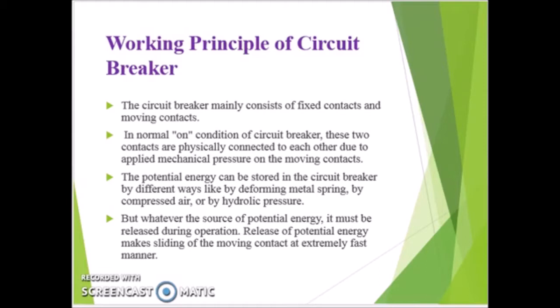In the previous diagram you see the metal spring, but whatever the source of potential energy, it must be released during operation. Release of potential energy makes the moving contact slide in an extremely fast manner. So there can be any operation depending on the arc quenching medium. As soon as the fixed and moving contacts move apart, there is an arc. As soon as the arc is produced, we have to quench this arc, we have to extinguish this arc.